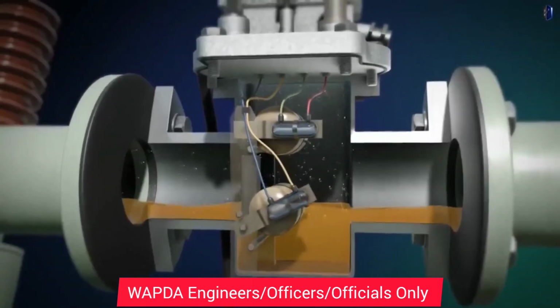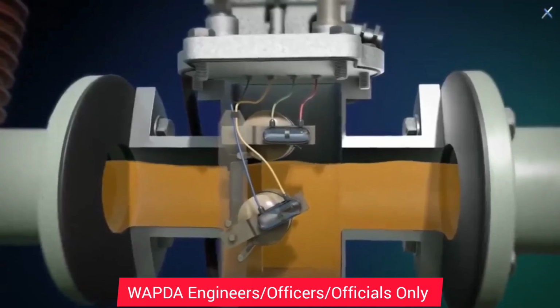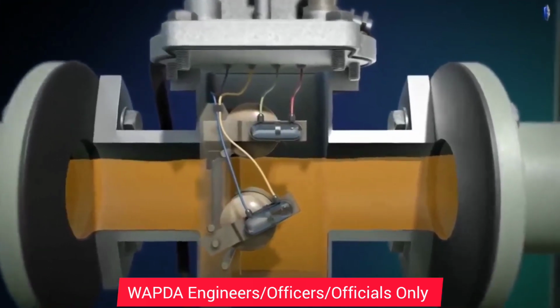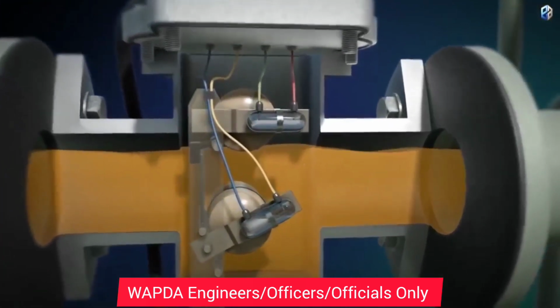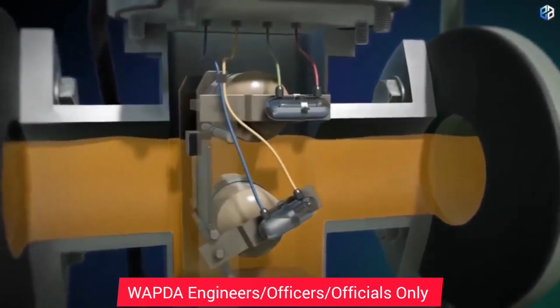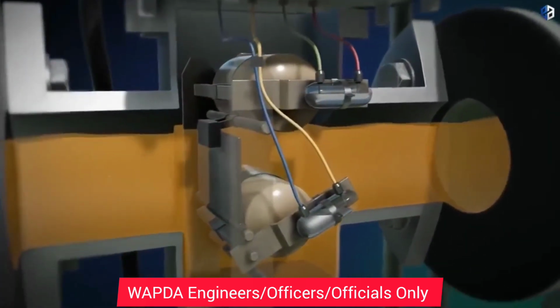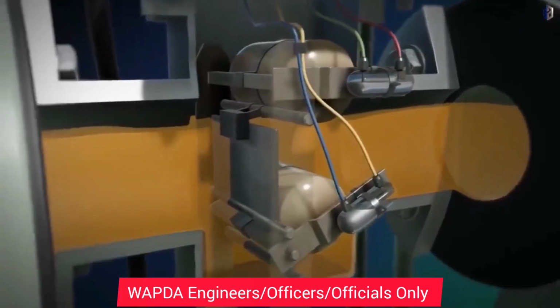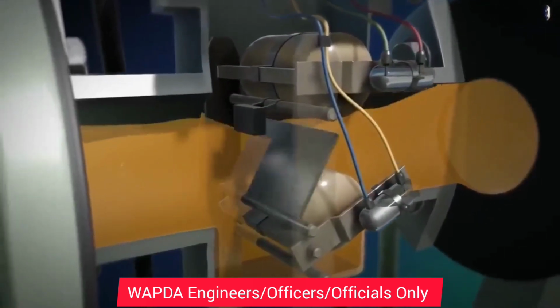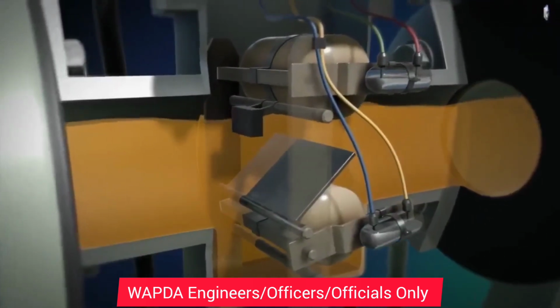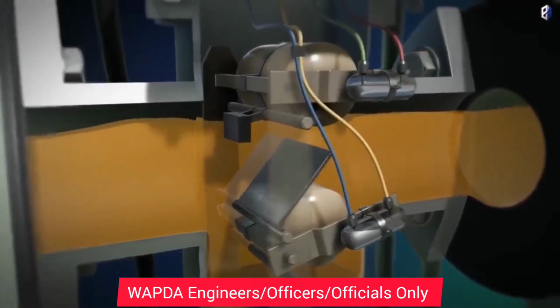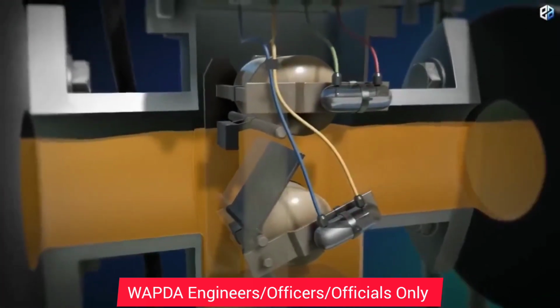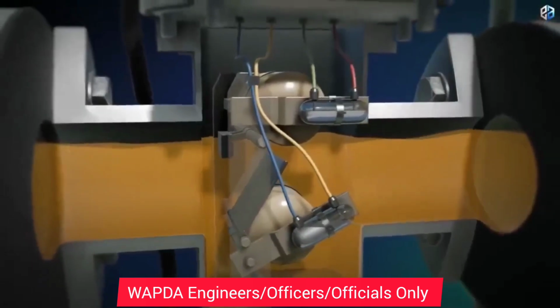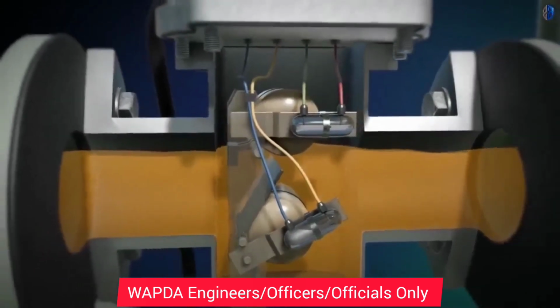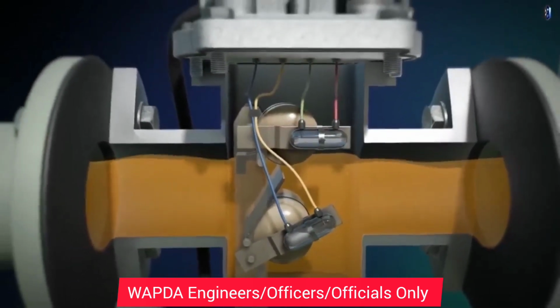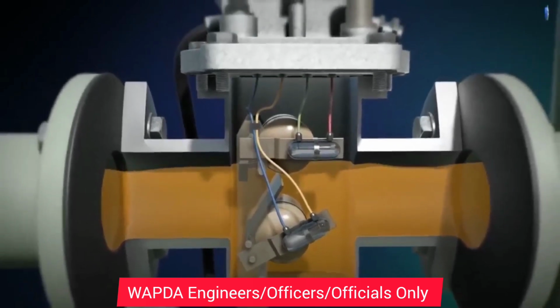If, on the other hand, a more serious fault occurs, that is a high current short circuit-like event inside the transformer, a rapid flow of oil occurs between the transformer and the expansion tank. This oil movement also passes through the Buchholz relay and hits a damper, which in turn actuates a switching mechanism. If this contact is activated, the Buchholz relay triggers an immediate switch off of the transformer, and the circuit breakers disconnect the system from the mains. The relay thus protects the transformer from further, more expensive consequential damage.